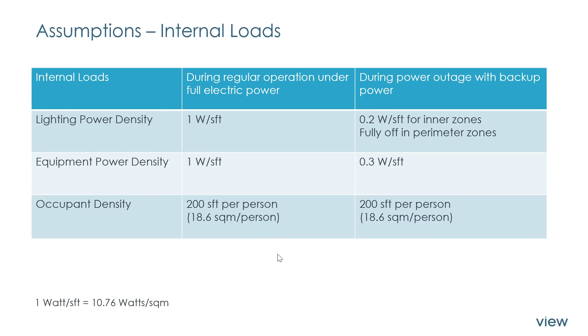However, the DOAS will continue to provide minimum outdoor air. This assumes there's some kind of backup power, or maybe the chiller failed or something. The logic is probably clear: if you're in an environment with a lot of people and you have no outdoor air and no operable windows, then frankly the indoor air quality might become a bigger problem than thermal comfort. So at that point, it's kind of unrealistic to expect any thermal resilience if you have no way to ventilate the building at all.